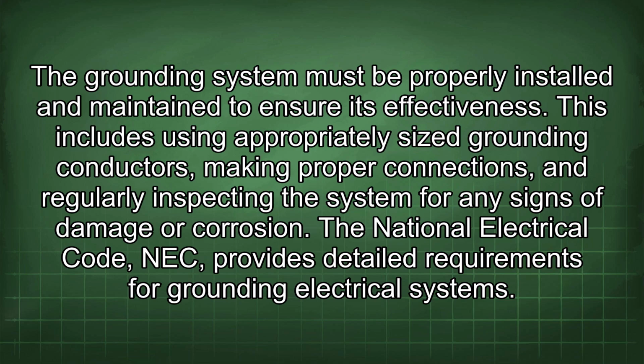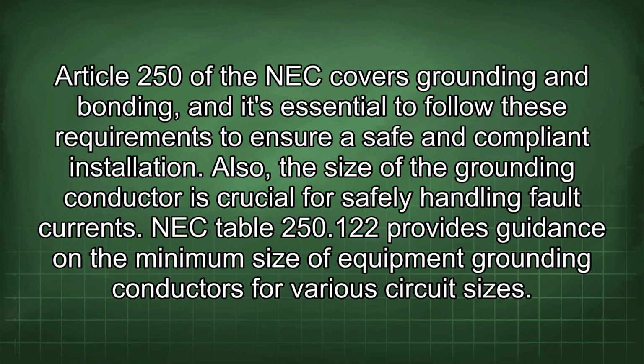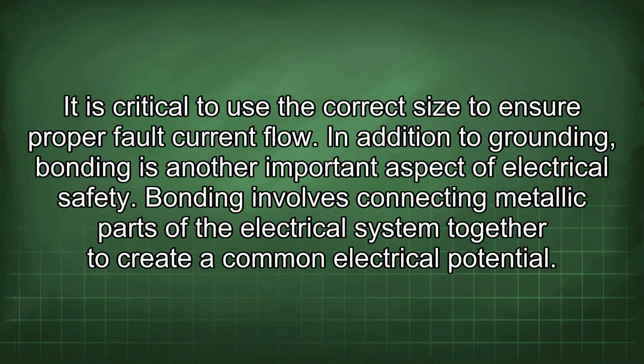This includes using appropriately sized grounding conductors, making proper connections, and regularly inspecting the system for any signs of damage or corrosion. The National Electrical Code, NEC, provides detailed requirements for grounding electrical systems. Article 250 of the NEC covers grounding and bonding, and it's essential to follow these requirements to ensure a safe and compliant installation. Also, the size of the grounding conductor is crucial for safely handling fault currents. NEC Table 250.122 provides guidance on the minimum size of equipment grounding conductors for various circuit sizes. It is critical to use the correct size to ensure proper fault current flow.